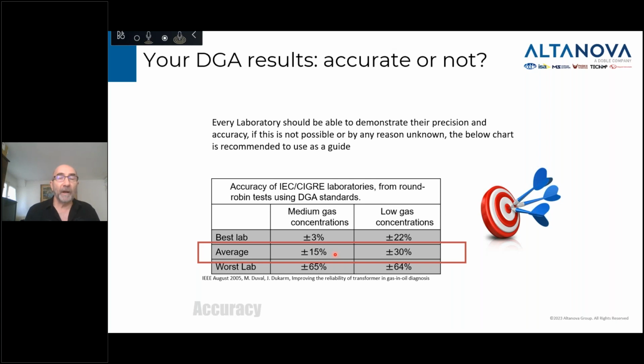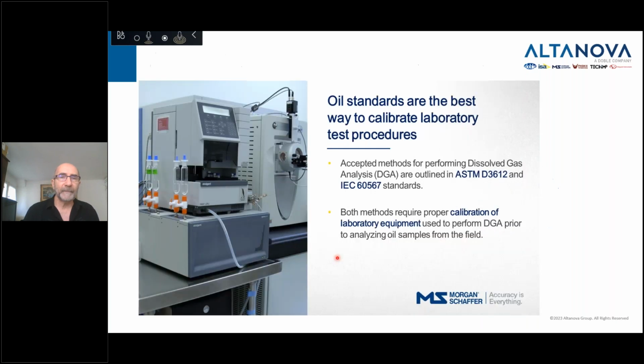And that's mostly in line with the IEC 60567. But when you look at the worst labs, some of those labs came back with results of plus or minus 65%. What it means is that for that lab, with the same sample that was sent to the other labs, their extraction system and their GC had an accuracy of plus or minus 65%. So if you send 100 ppm, they measure only 35 ppm, meaning that, frankly, you cannot do anything with that result as far as diagnostics. So what this shows is that it's very important, when you choose a lab, to understand their accuracy, especially at the medium gas concentration, and to make sure that they're under that 15%.